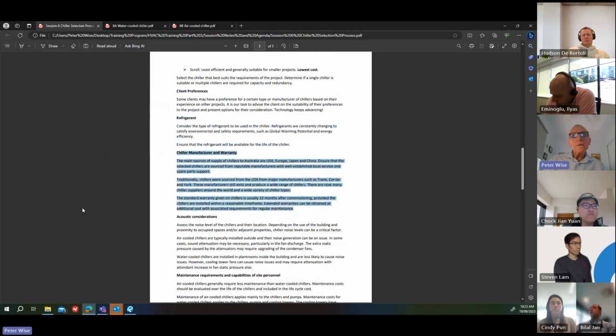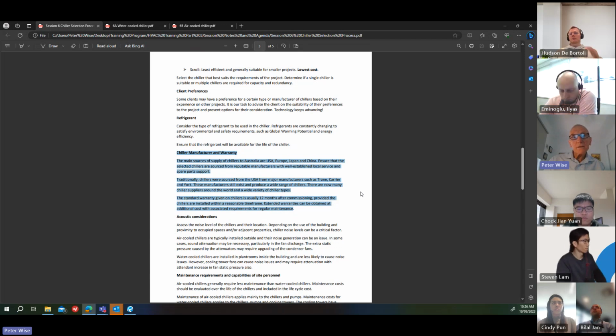Chiller manufacturer and warranty. The main sources of supply of chillers in Australia are from the USA, Europe, Japan and China. Ensure that the selected chillers are sourced from reputable manufacturers with well-established local service and spare parts support. This is important for the ongoing maintenance of the chiller. Generally, the people who offer you chillers will be well established in Australia, but there are others, and if they're not well established, they don't have a good backup of service and spare parts, then you're probably better not to deal with them. Traditionally, chillers for Australia were sourced from the USA, from major manufacturers like Trane, Carrier and York. These manufacturers still exist and provide a wide range of chillers. They also have plants in other parts of the world. They have factories in France and Italy, for instance, where they make different types of chillers, as well as in the USA.